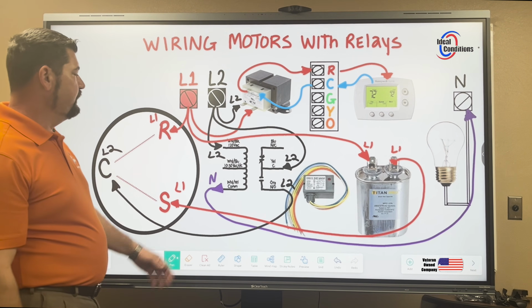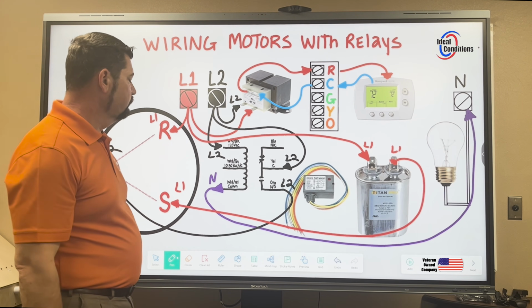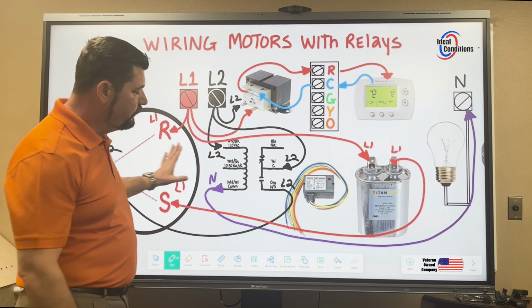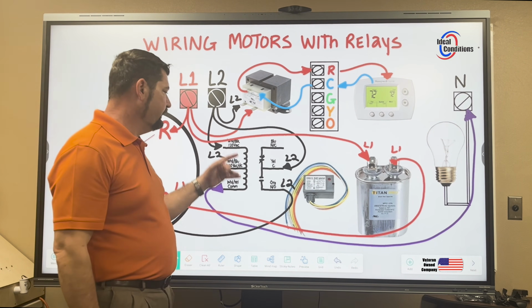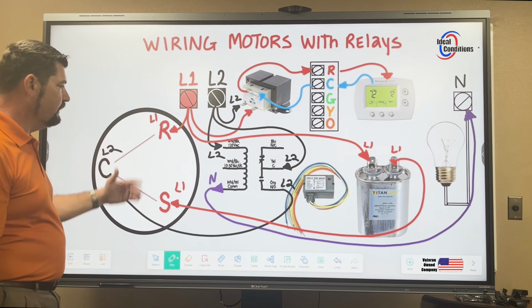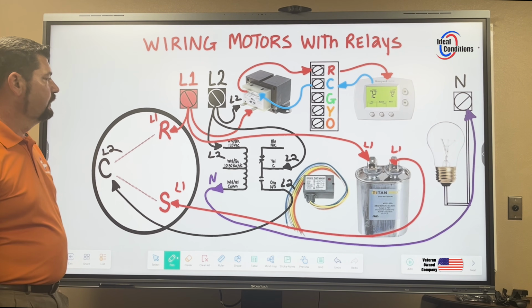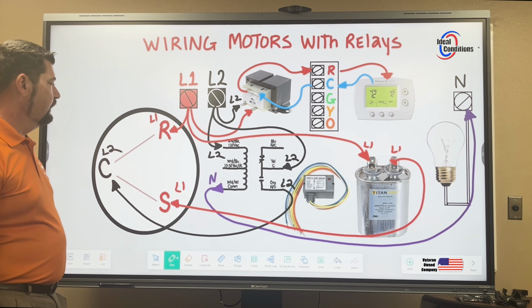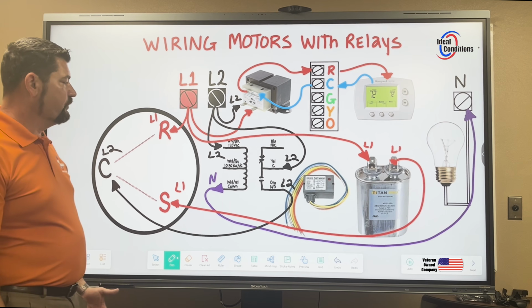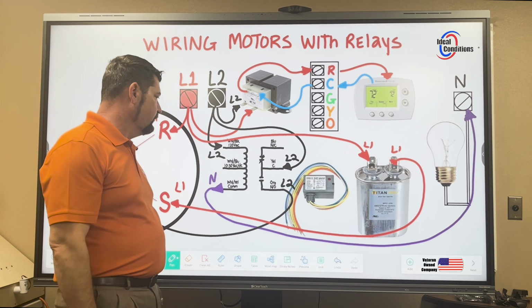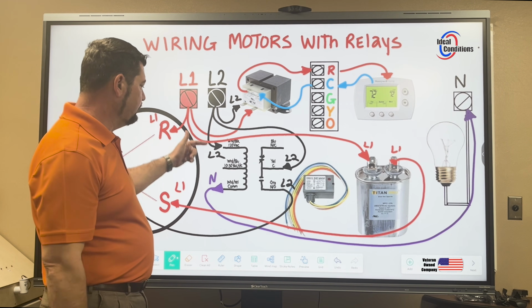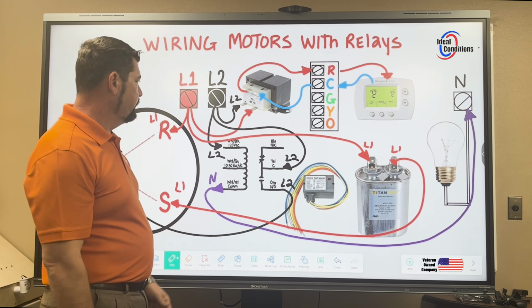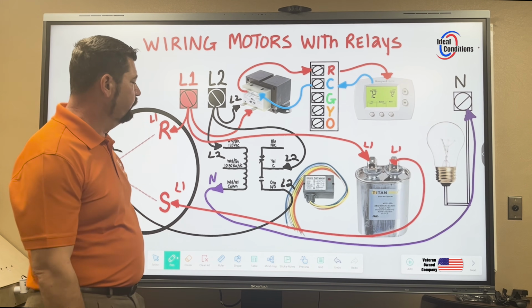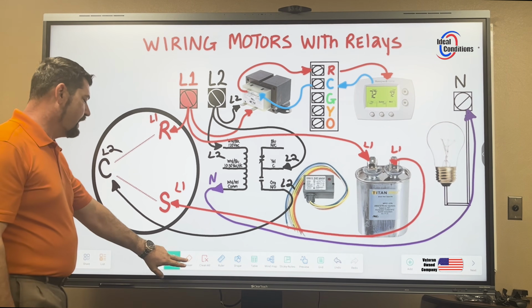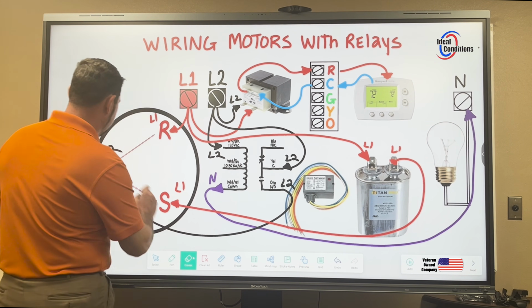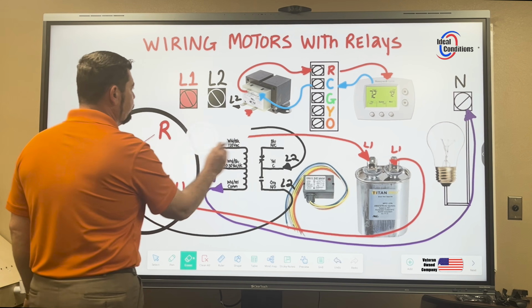Doesn't make a whole lot of sense because there's nothing to drop out neutral. There's nothing to drop out L2. So the way we have this wired up, and definitely we would have coil voltage, and then definitely the motor would run. So we wouldn't do it that way. But I'm just trying to demonstrate, could I get this to come on if I landed L2 here? Sure, but there's nothing here to break L2. So we would not do that.